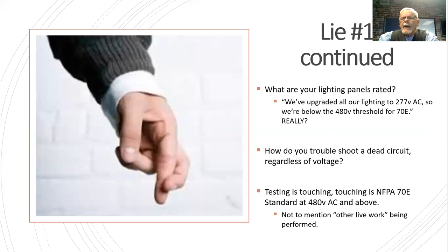And then, of course, you ask, well, if you have something that needs to be looked at, you have to troubleshoot it. You can't troubleshoot a dead circuit. I don't care what the voltage is. If it's dead, you've turned it off, you can't troubleshoot what the problem is. Therefore, your qualified electrical workers are going to be testing.